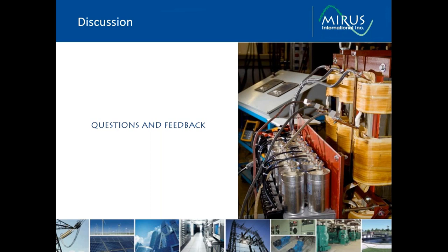Thank you, Gennaro. The first question we have asks, what instrument do you use to measure harmonics above the 50th harmonic? This is an excellent question because there are not that many instruments on the market today that measure above the 50th. There certainly are a few, though. I know that there's an Elspec meter that will measure above the 50th. There's a Dranetz meter that will measure above the 50th. There's a PQube meter that measures above the 50th. So there are a few of them out there, but you have to look hard to select them.